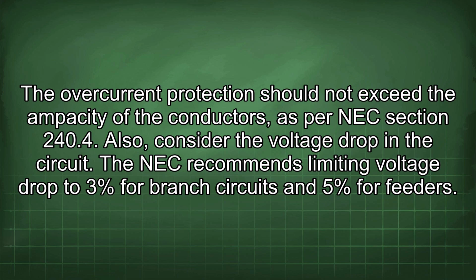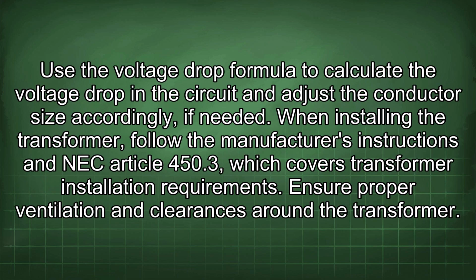Also, consider the voltage drop in the circuit. The NEC recommends limiting voltage drop to 3% for branch circuits and 5% for feeders. Use the voltage drop formula to calculate the voltage drop in the circuit and adjust the conductor size accordingly if needed. When installing the transformer, follow the manufacturer's instructions and NEC Article 450.3, which covers transformer installation requirements.